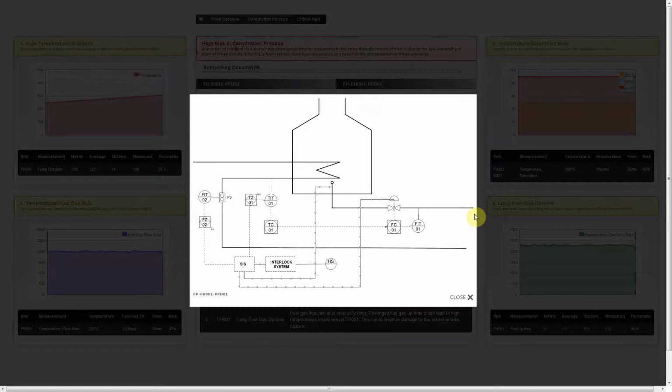So because fuel gas was on but there was no regeneration gas, the temperature skyrocketed inside the fired heater, and our SIS just wasn't able to react quickly enough. In the space of a few hours, the tubes inside ruptured, the temperatures reached uncontrollable levels, and the top half of the fired heater fractured, flying into the air and landing in another part of the plant.